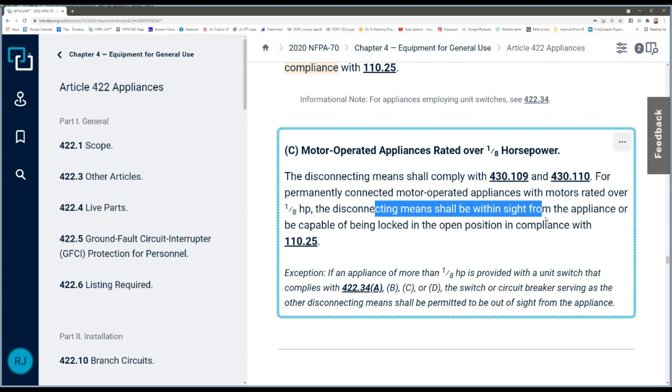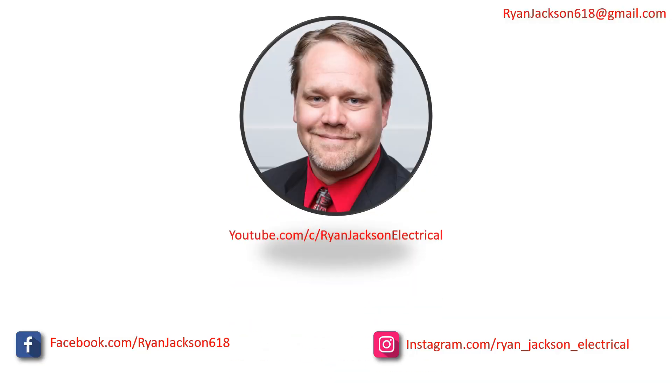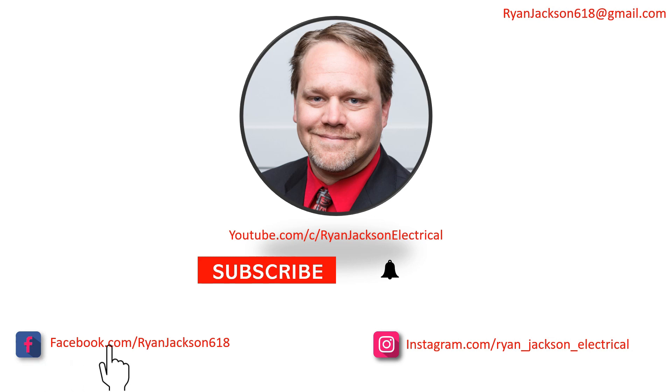For a motor-operated appliance rated over 1/8 horsepower, it's essentially the same: the disconnecting means must be within sight of the appliance or capable of being locked in the open position. What that means practically: you need a disconnect on the outside for the compressor unit, and make sure it's lockable. As long as you buy a disconnect with a lock hasp so you can slip a padlock on it, that outside disconnect satisfies the requirement for the inside disconnect for the interior unit as well.